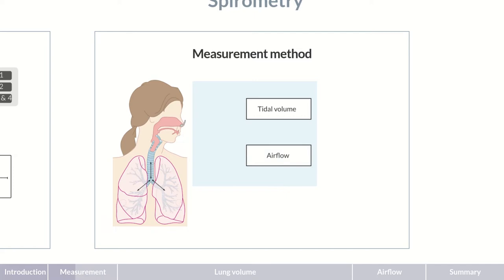One means of measurement is to detect the rotation speed of a turbine, which can be used to deduce the volume breathed. The second means is by using a resistor in the mouthpiece to observe pressure changes. By measuring pressure before and after resistance, the difference between these values can be used to determine the airflow.